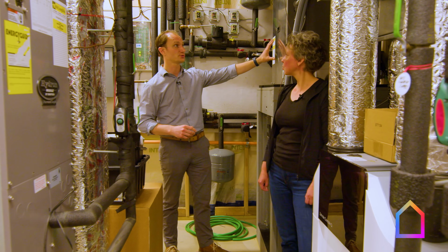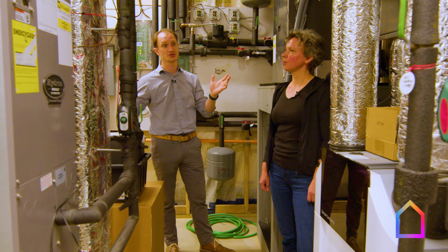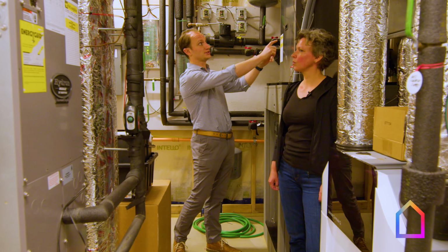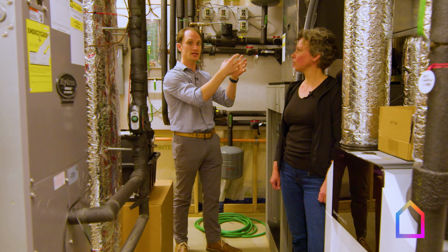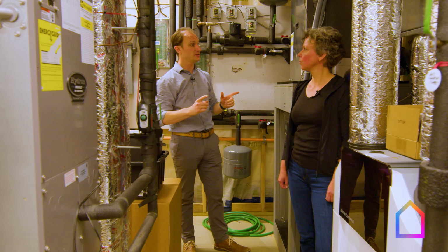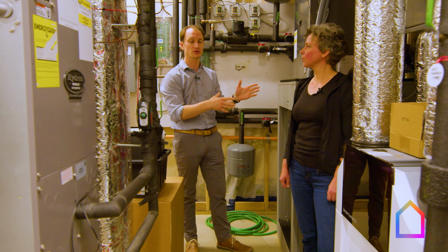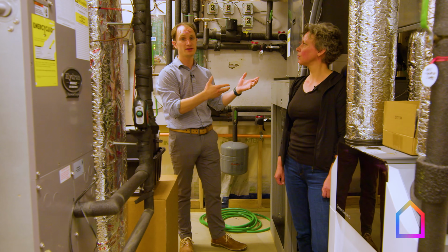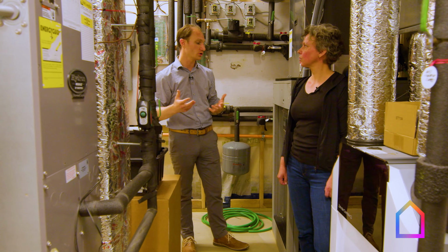With the 3 ground source heat pumps, instead of running refrigerant lines throughout the building, having multiple sources of potential leakage of that refrigerant, the refrigerant is all housed inside these units, factory sealed in a small area. So a tiny amount of refrigerant, and we're running hot and cold water lines throughout the project. It did increase the initial cost of that system. However, there's a lot more flexibility with this system as the parts are interchangeable, and we're expecting a longer life out of this system and it's easier to maintain over longer periods of time.